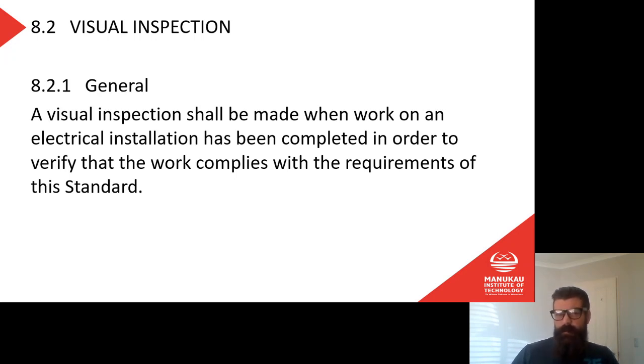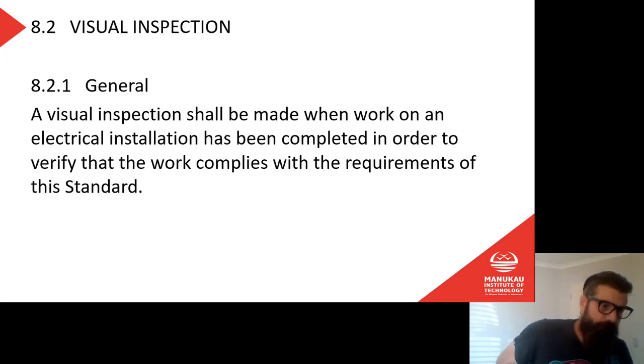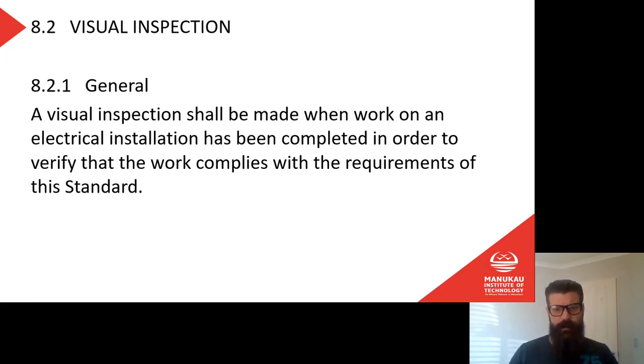What would we cover in a visual inspection? We need to check that we've connected the right conductors to the right place. Is the red wire going to the right place? Does the black wire go to the right place? That's a really easy way for us to pick up if there's any faults, right? I just go and have a look. I look at all the sockets and go, yep, they're in the right place. That one's in the right place. I can go and look in the switchboard and make sure, is all the power going through the main switch? Are all the green wires connected to the earth bus bar? You know, that kind of thing. So visual inspection, while we kind of take it for granted, and I guess in a way while you're doing the work, you're kind of completing your own visual inspection, but it is a really important thing that we need to do.